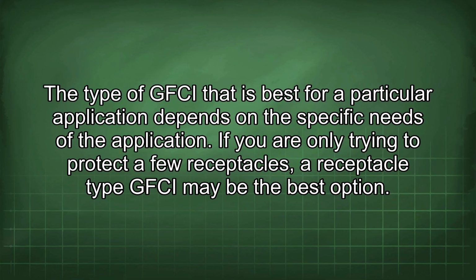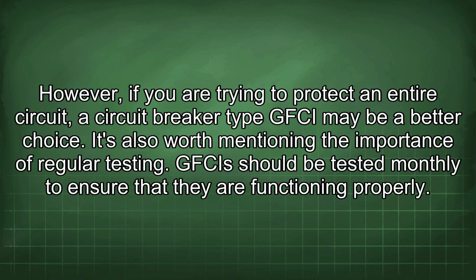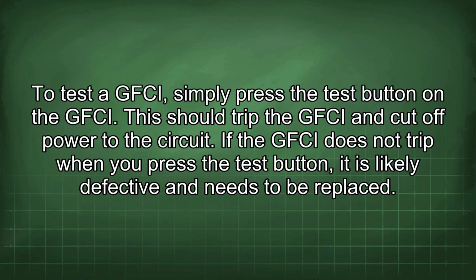The type of GFCI that is best for a particular application depends on the specific needs of the application. If you are only trying to protect a few receptacles, a receptacle type GFCI may be the best option. However, if you are trying to protect an entire circuit, a circuit breaker type GFCI may be a better choice. It's also worth mentioning the importance of regular testing. GFCIs should be tested monthly to ensure that they are functioning properly. To test a GFCI, simply press the test button on the GFCI. This should trip the GFCI and cut off power to the circuit.